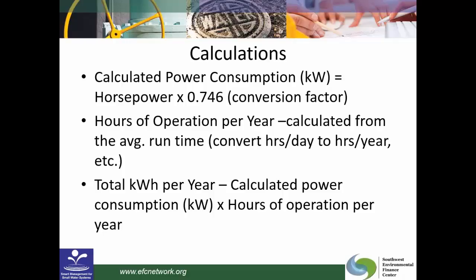Then you want to take your hours of operation per year, and that comes from your average runtime. So if you had hours per day, you want to get it to hours per year. That can be a simple direct input or a simple conversion. Then you want to take your total kilowatt hours per year. So you're going to take that first one, the calculated kilowatts, and multiply it by your hours of operation per year.